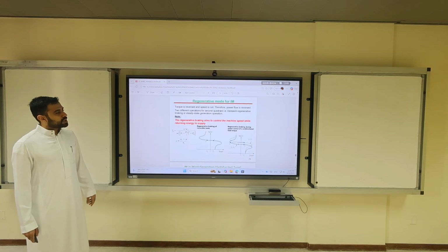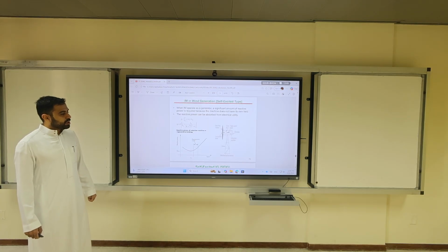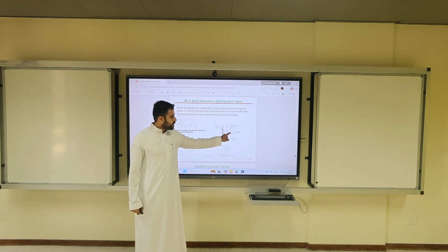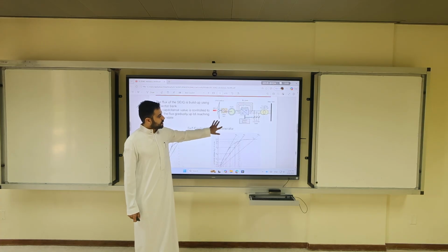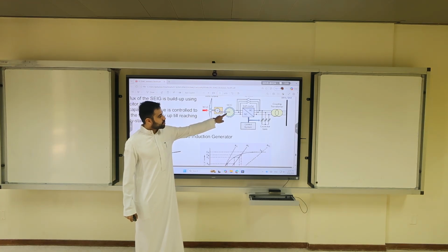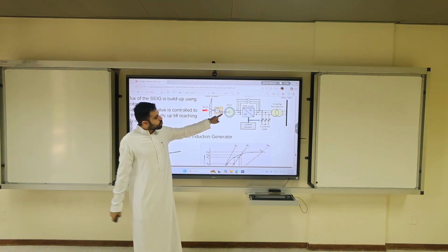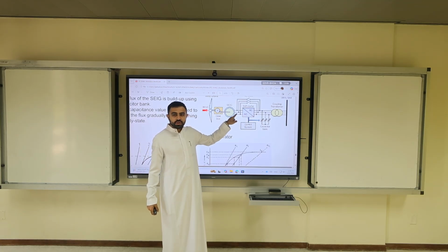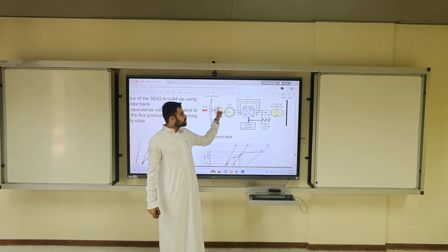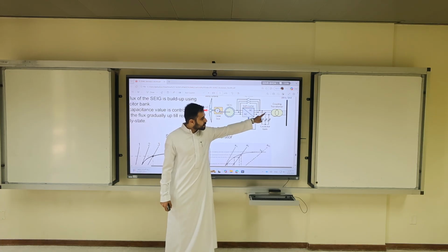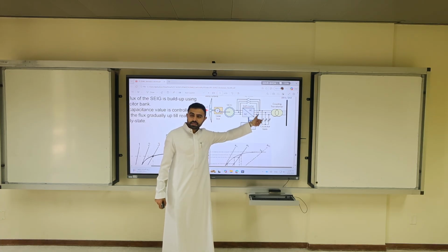Last time we talked about the IGs for a wind turbine, and I explained that we have a gearbox and an induction generator. However, this is not everything. We tend to have the gearbox and the squirrel cage induction. Squirrel cage is self-excited. We connect it to an AC to AC converter. It converts the frequency from whatever speed generated to 60 Hertz. And we put capacitor banks to inject VARs in the system.